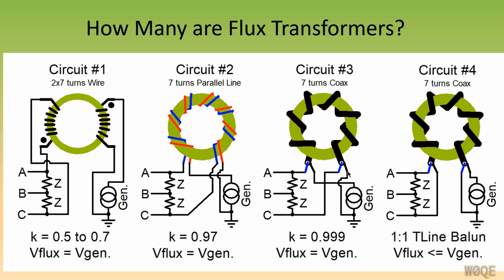Now, in this case, the generator drives the shield on both ends, and we take the output off from the center conductors. It could have been the other way around, it wouldn't have mattered. In this case, we have extremely good coefficient of coupling. Again, the flux in this core is exactly the same as all the others, it's just the generator voltage.